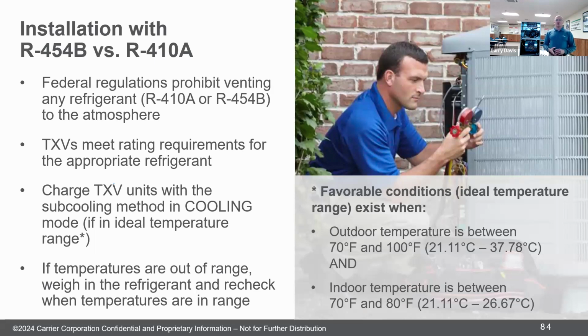You charge in the subcooling mode with the TXV, that hasn't changed. You want to look for the ideal temperature range, which means 70 to 100 degrees outside and 70 to 80 inside. If you're not within those ranges or can't get within those ranges, weigh the charge in. Always come back on a day that you can get within those temperature ranges and double check your subcooling.